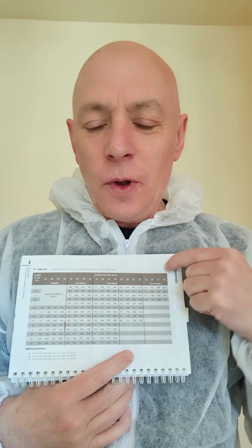So for example, here we've got 1 bend, 2 bends, 3 bends, that's missing, you might want to write that in, and then 4 bends. Although you can use 4 bends, I'd recommend from experience, it's really tough pulling the cables in, so I'd avoid using 4 bends wherever possible. Okay, so that's a really important thing.